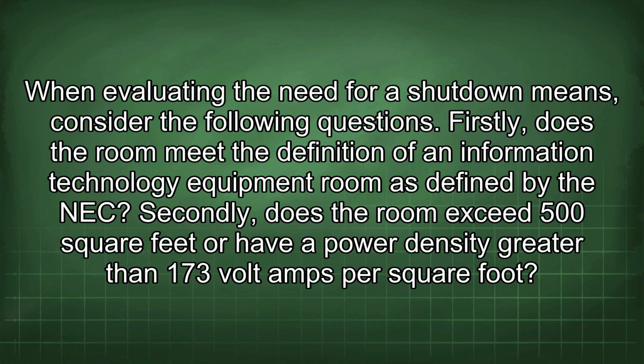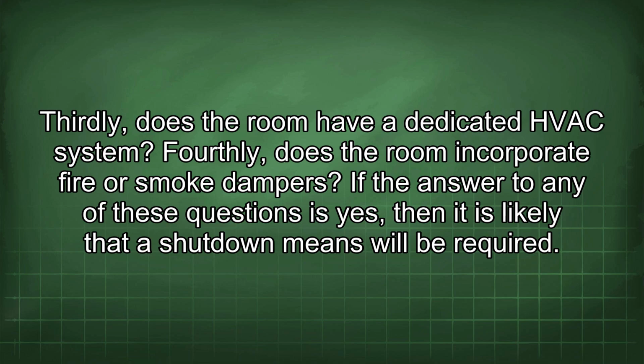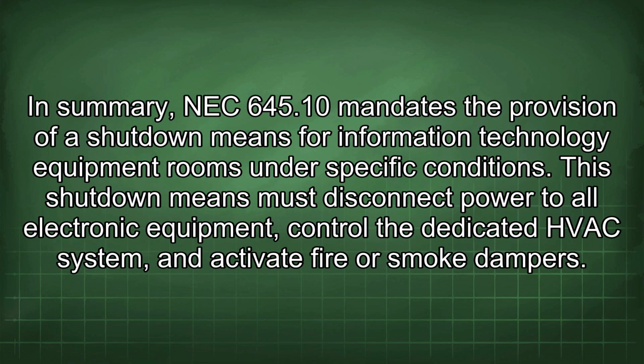Secondly, does the room exceed 500 square feet or have a power density greater than 173 volt-amps per square foot? Thirdly, does the room have a dedicated HVAC system? Fourthly, does the room incorporate fire or smoke dampers? If the answer to any of these questions is yes, then it is likely that a shutdown means will be required. In summary, NEC 645.10 mandates the provision of a shutdown means for information technology equipment rooms under specific conditions.